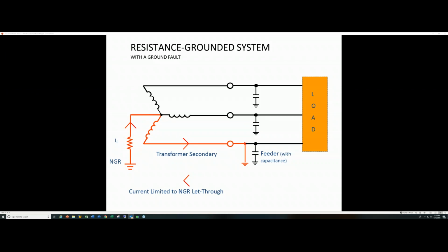All right, now that includes the feeder capacitance and all that, but let's just say for simplicity, you've got a fault to ground, goes through the resistor and comes back. Well, we can control the resistor. So your I sub G of F, we can absolutely take care of that and limit it to only 10 amps or less. Now think about it. If you had a choice, I have a fault and I only have 10 amps. That's a whole lot less arc flash, minimal to none, and a whole lot less personnel injury and a whole lot less equipment damage, on and on and on.